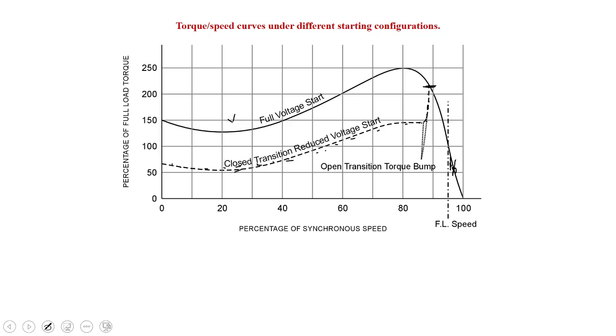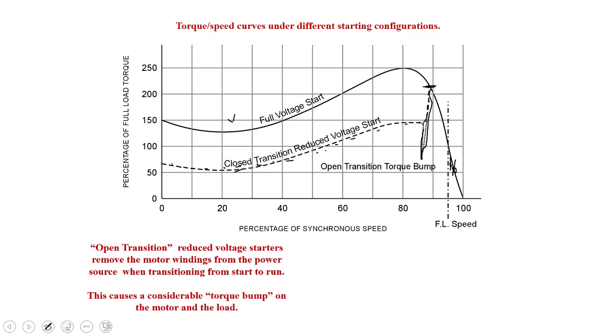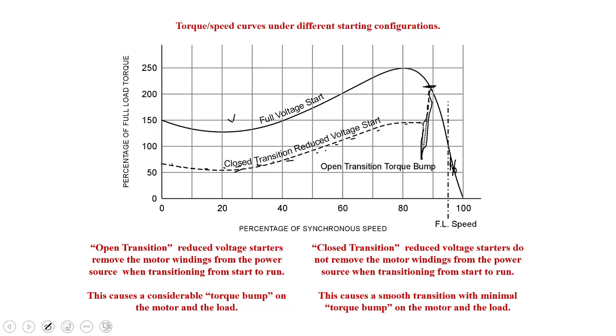If this was an open transition and we reduce the voltage for a second before we switch to full voltage, we'd see that torque go down really quickly, decelerate this motor, and then all of a sudden, boom, it spikes right back up. So we get what's called a torque bump there. So a little bit about this: it's a lot smoother transition if we have a closed transition starter.